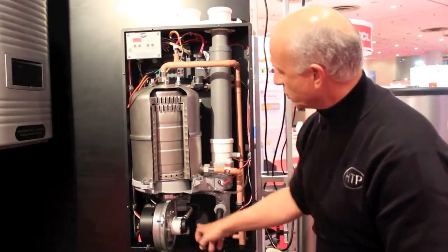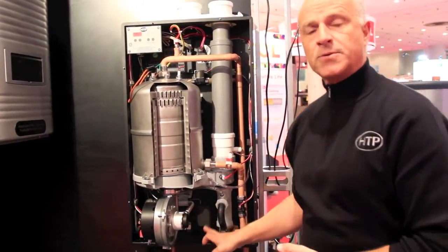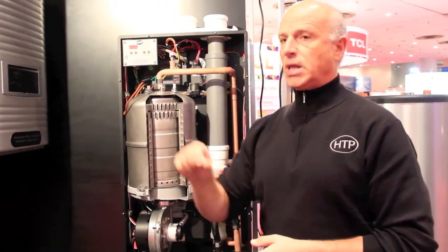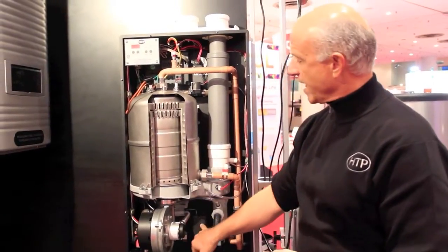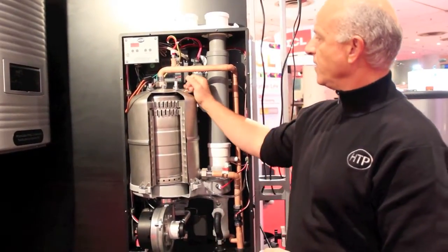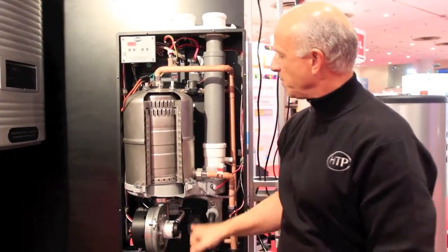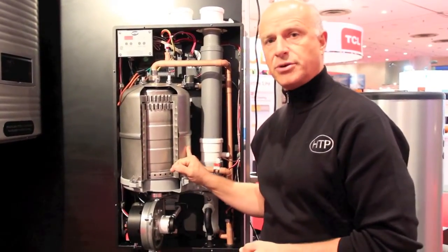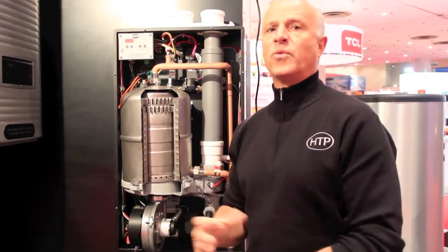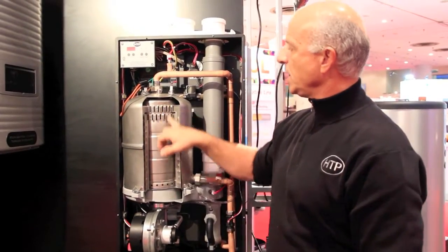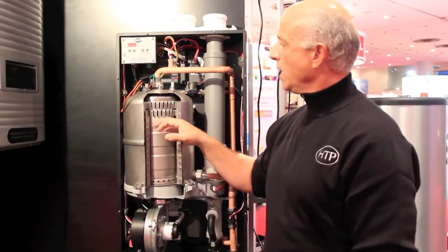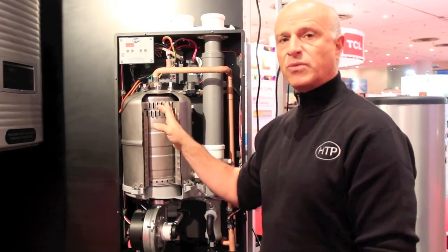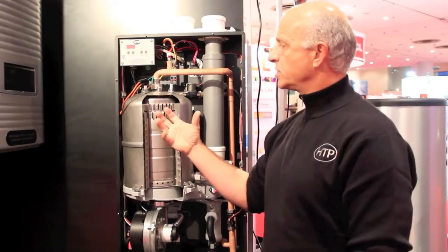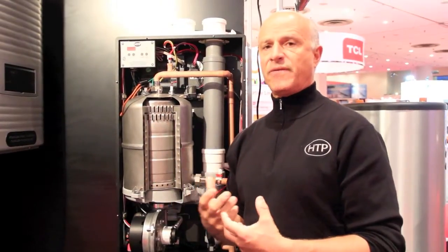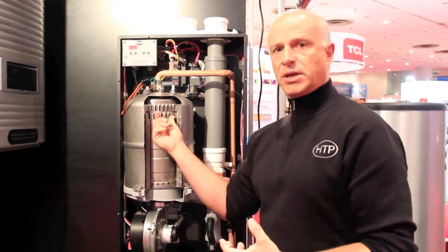Some of the unique features is we're going to have a built-in pump to this system. So customers that want to have recirc in their house where they have a long run and it takes a lot of time to get hot water, this will already have that built in. And we have this little solenoid valve, and this pump also provides stabilization of this heat exchanger. So when the unit shuts down, you'll have some heat stratification in this unit, and that heat will build up over time if we don't circulate the water. And in some areas where you have a lot of lime and you have very aggressive water, that can affect the heat exchanger over time.